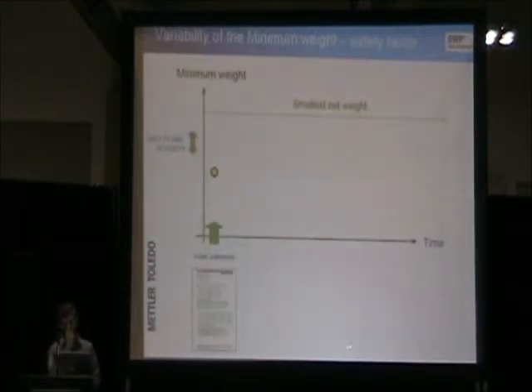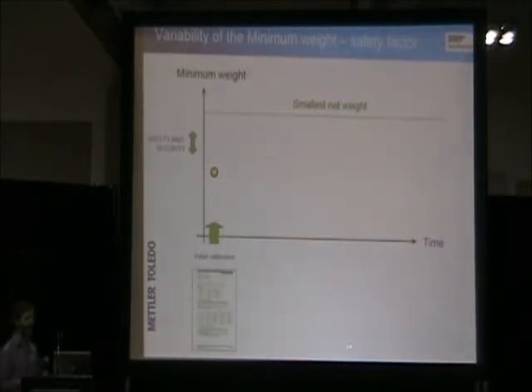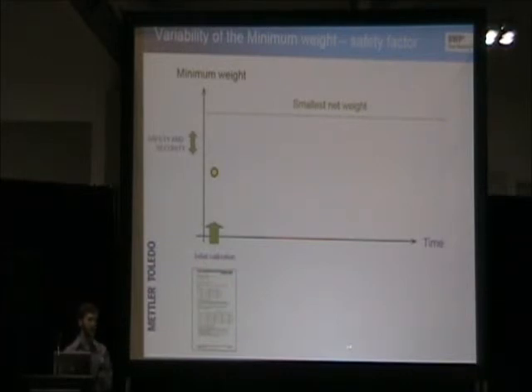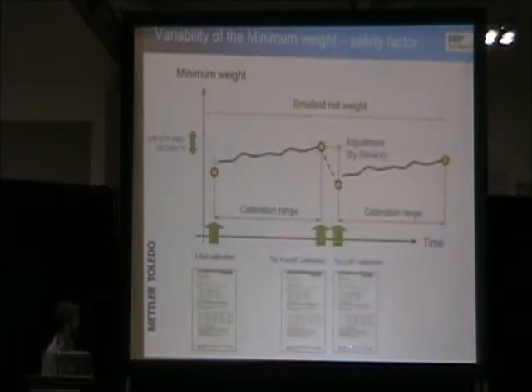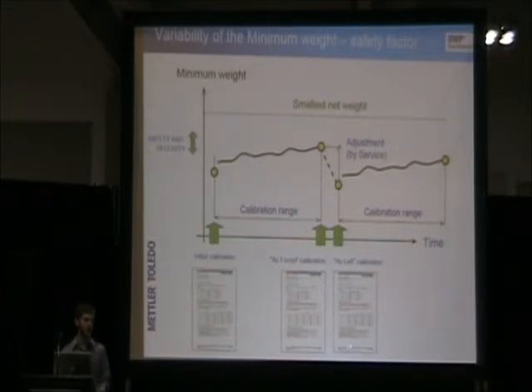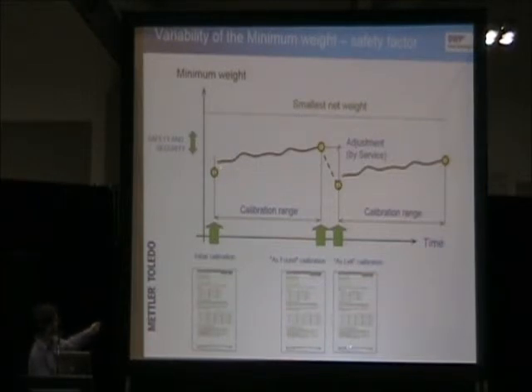So let's give an actual example of the deviation that can occur from a calibration that is performed initially when you install your balance, and what will happen throughout, let's say, a 6-month period in between calibrations. So for this example, you establish 30 milligrams on your analytical balance. You have 6 months of use throughout that, where there's environmental changes, the changes in temperature and humidity outside, and the seasons are changing. Maybe you have a new technician that comes in that has an off-weighing technique and is inducing a lot of uncertainty. Or maybe your facility isn't temperature and humidity controlled and there's a lot of fluctuations throughout the day. Throughout those 6 months or 3 months or 12 months, your actual minimum weight is going to increase or deviate.